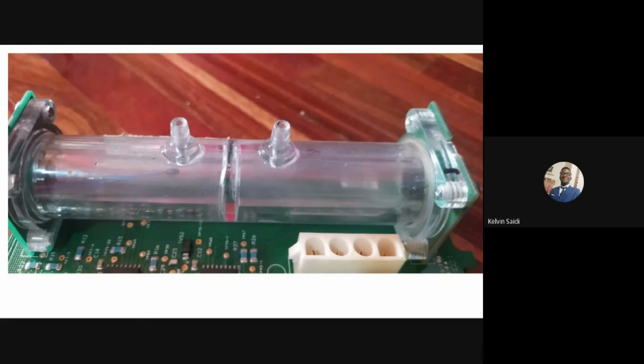They are more stable. They also produce measurements with a high degree of accuracy. They are also long-lasting, and they can measure both flow and concentration simultaneously. So you don't have to buy a flow sensor. You can have one ultrasonic sensor and use it to measure concentration and flow at the same time. The primary drawbacks are that ultrasonic sensors are affected by moisture, and they also have a flow limit of 10 liters per minute. And when you exceed this limit, you get very inaccurate readings, or unreliable readings, I should say.